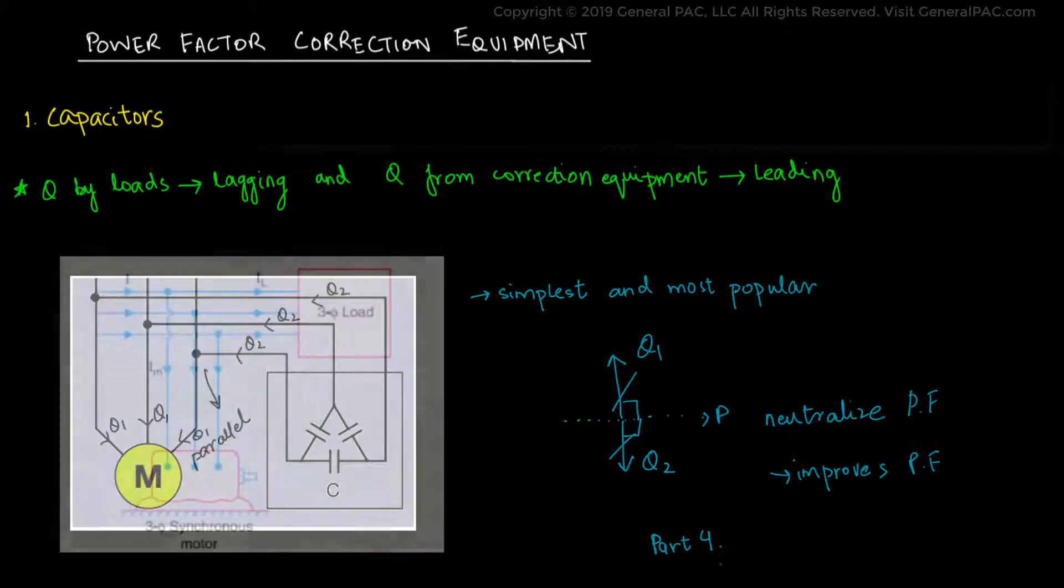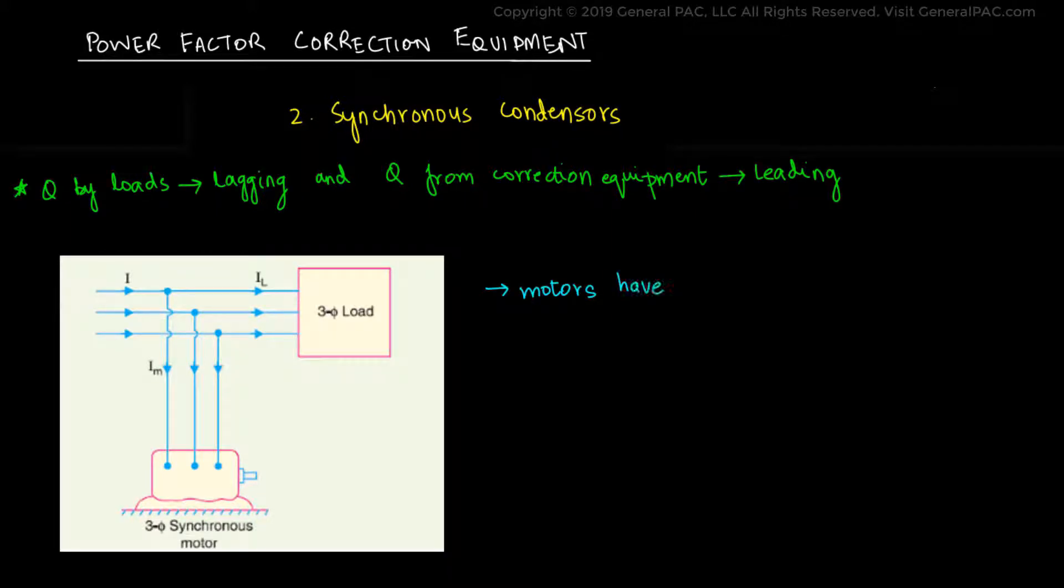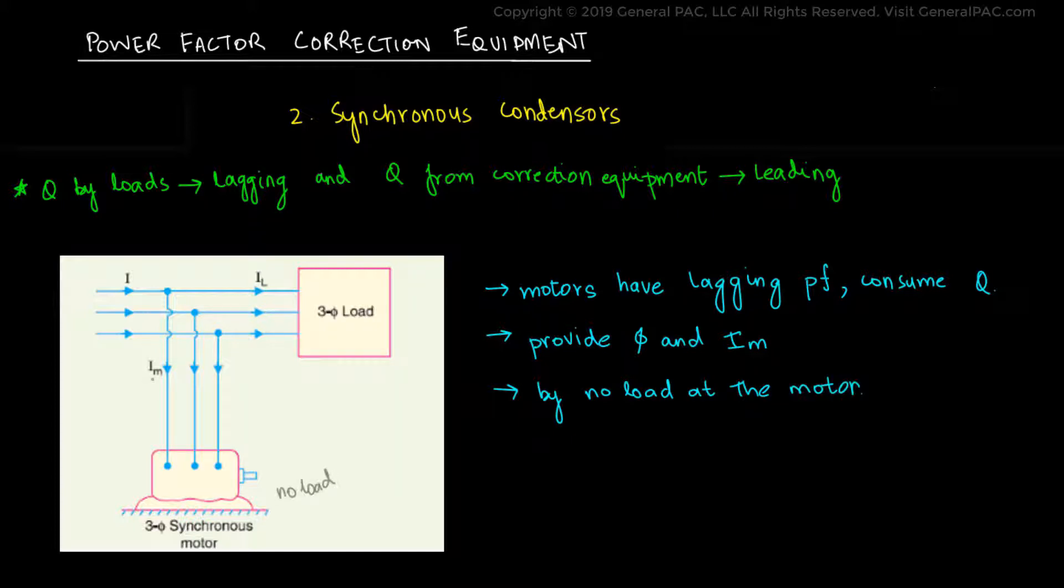The next one is called a synchronous condenser. We already know from the previous parts that motors have lagging power factor and they consume reactive power. But what if we were to provide an additional magnetic flux than necessary? And in addition to that, we remove any loads attached to its shafts. The additional magnetic flux would then cause the motor to start supplying reactive power instead of consuming it as the case originally.